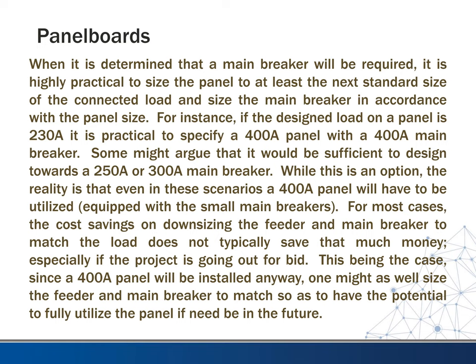So on bid day, it about all counts the same. So you're not really saving any money, you're just limiting your capacities. So this being the case, since a 400 amp panel will be installed anyway, one might as well size the feeder and the main breaker to match so as to have the potential to fully utilize the panel if need be in the future.